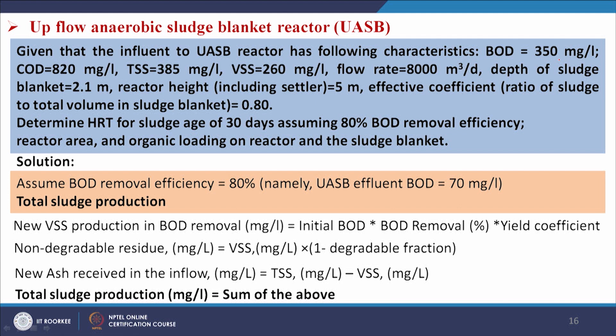Now we will solve a numerical problem. Given: influent BOD = 350 mg/L, COD = 820 mg/L, TSS = 385 mg/L, VSS = 260 mg/L, flow rate = 8000 m³/day, depth of sludge blanket = 2.1 m, reactor height including settler = 5 m, effective coefficient = 0.80. Determine HRT for a sludge age of 30 days assuming 80 percent BOD removal efficiency, reactor area, and organic loading on the reactor and sludge blanket.